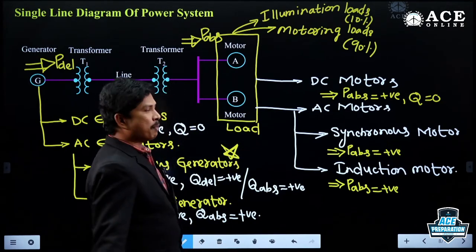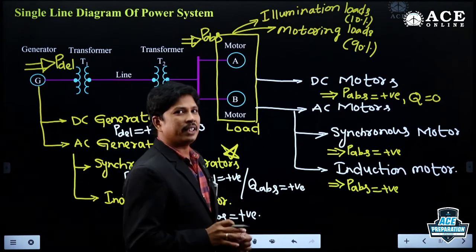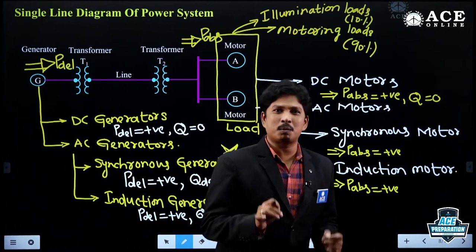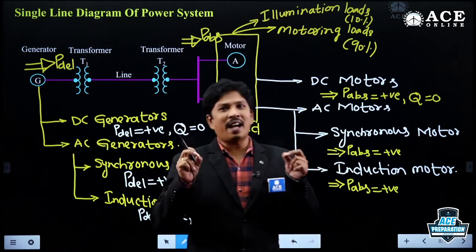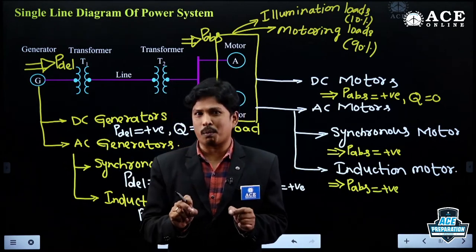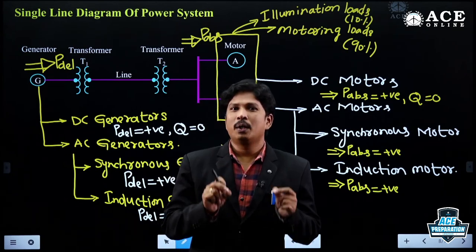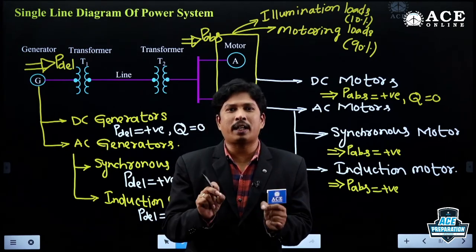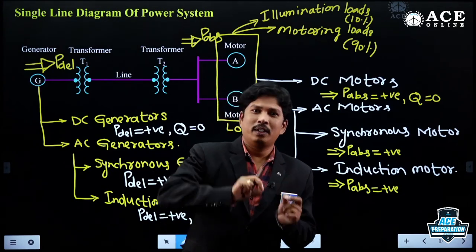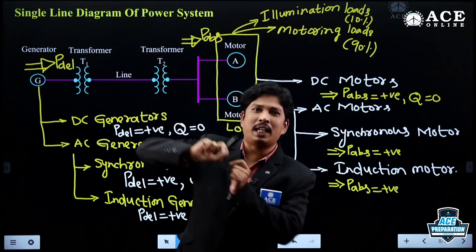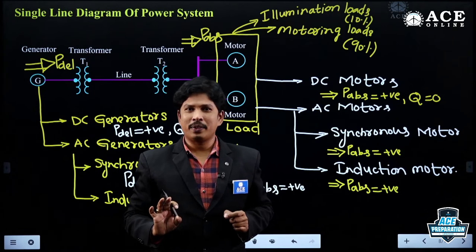And coming to the AC motors, the synchronous motors are having the excitation again, so we can control the excitation of the synchronous motors also. Therefore, we can operate the synchronous motor so that it can deliver reactive power or absorb reactive power as it takes up. Are you getting the point?